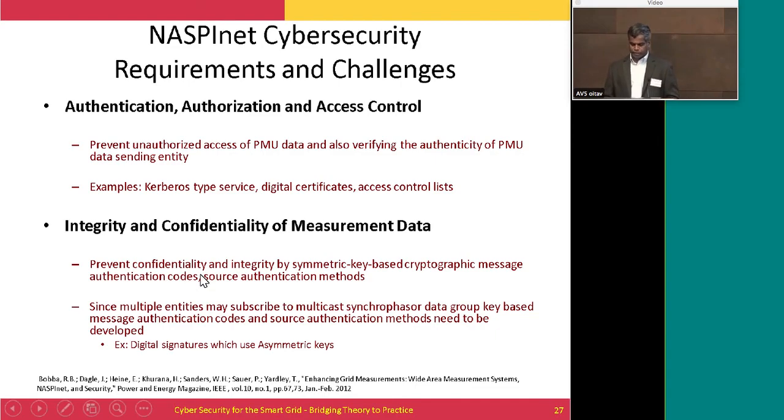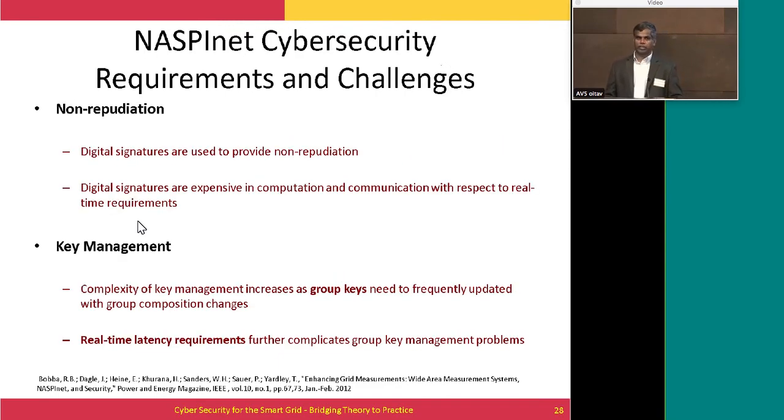Then integrity and confidentiality of measurement data, that is important as well. Symmetric key-based cryptography is used for achieving confidentiality. Then some kind of hashing techniques and digital signatures are used to achieve data integrity and other kinds of authentication in the systems. Those are all in place. So traditional cybersecurity technology, IT security solutions, can very well be adapted because this phasor gateway data bus is not within the utility environment. It is across utilities. They don't have tight timing constraints. They are more coarse-grain applications for which these kinds of technologies can be adaptable because they are high-end devices as well. Non-repudiation: digital signatures can be used to provide non-repudiation service. Sometimes it may be expensive. There are lightweight technologies that can be adapted.